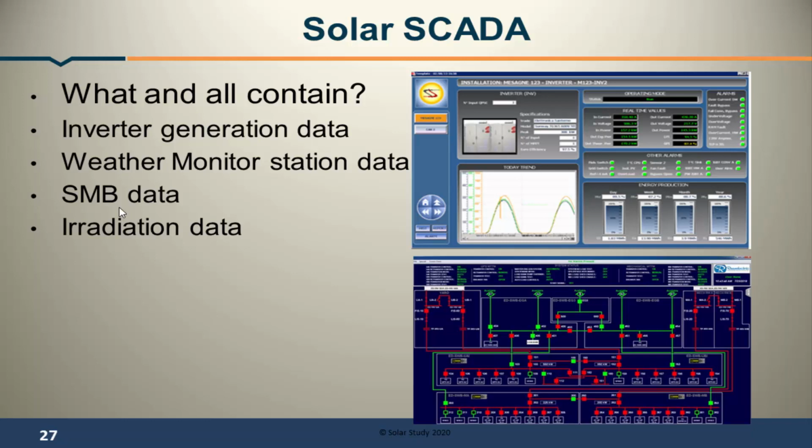That is the wire coming from the solar panel or array of panels. Each string contains around 20 to 40 modules. So one string containing 40 modules, there may be 12 strings present in 1 SMB. So 40 into 12, 480 panels in 1 SMB.